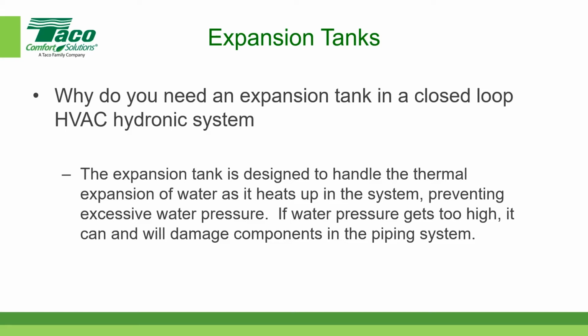This paragraph talks about heating up the water, so some of you may wonder, do I need an expansion tank for chilled water, since I'm not really heating that up? Well, Rich and I have talked to people this has happened to. They design a system, and it was undersized, maybe they put in a small expansion tank for a chilled water system. But there are times that chilled water system may not have the chiller running, especially during installation. Many of us have been on projects where the piping's done, the water's filled up, and the chiller isn't turned on for 6 or 8 months. That water can well see 100 degree temperatures, so that same phenomenon of the water heating up still applies.